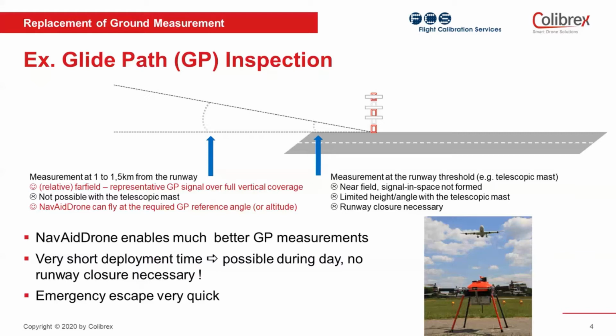Whereas with the drone, we can, for example, go a bit farther away, typically 1 to 1.5 kilometers from the threshold. This would be at the middle marker. And here we get a representative glide path signal over the full vertical coverage, which is obviously not possible with a telescopic mast. The NavAidDrone can then fly the complete reference angle that is necessary.